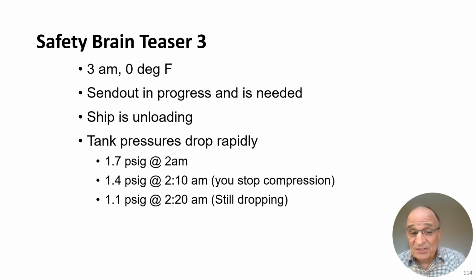Now, when I say PSIG, you realize we're talking about differential pressure and it's still dropping. What could be happening? When I say differential pressure, I'm talking about the difference between the tank pressure and the outside barometer. But I didn't say that to give you any kind of a direction to go in. You've got to consider what could be happening in this very short time frame that the pressures are dropping so quickly.